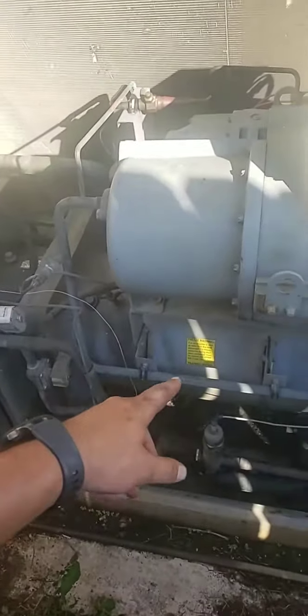As the oil gets ran through the motor, or the bearings on the compressor, it hits this port, and it's got a series of casted trails that it flows through, just kind of like a car motor does, and it flows down on top of the bearings throughout the motor. Now all that oil gets sent back out through the discharge. And so that's when it hits your oil separator, which, like I said, we'll get to shortly. I don't want to come off of here too quickly and bounce back and forth. So that's your overall compressor.